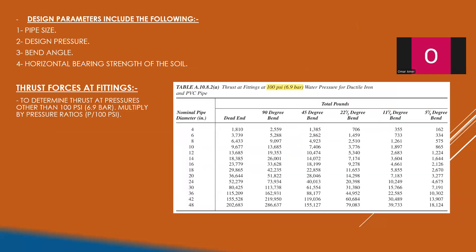The main parameters to prepare or implement a design for a thrust block are: first, the pipe size; second, the design pressure; third, the bend angle; and fourth, the horizontal bearing strength of the soil. These are the four main parameters. As the bend angle increases, the thrust force will be higher.